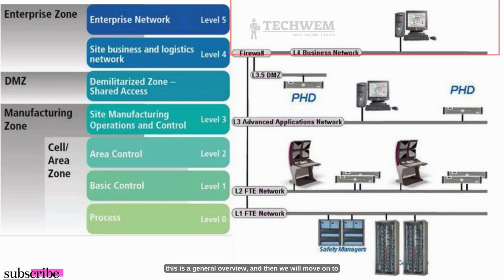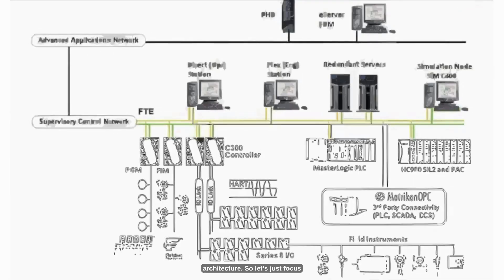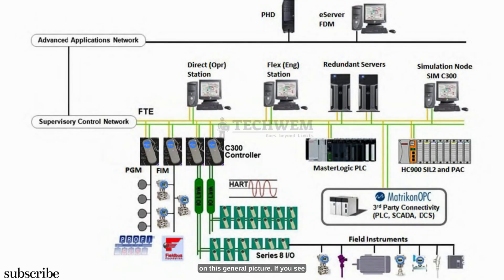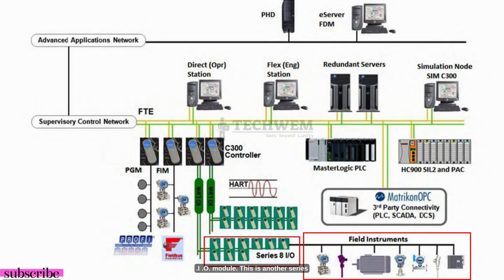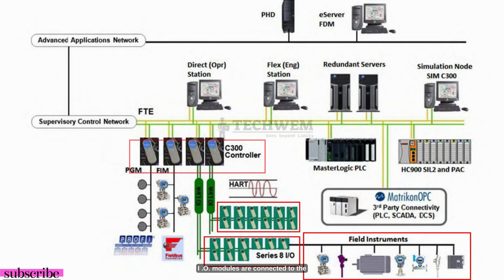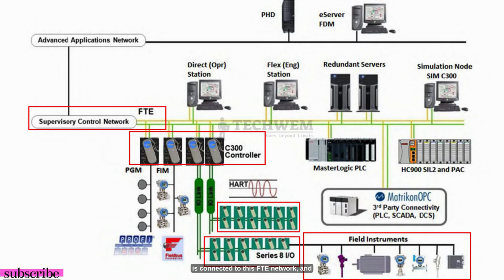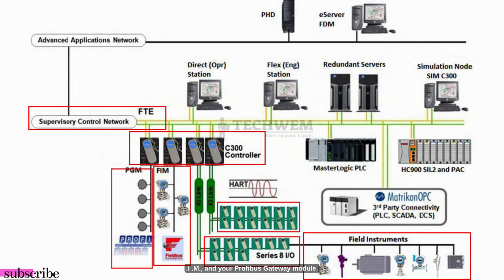This is a general overview, and then we will move on to Honeywell DCS Control System specific architecture. From the bottom, we have field instruments coming in. Those field instruments are connected to the I/O modules — these are Series 8 I/O modules, they could be Series C I/O modules. Those I/O modules are connected to the DCS controllers, and that controller is connected to the FTE network. The same goes for your Fieldbus devices, FIM, and your Profibus Gateway module.